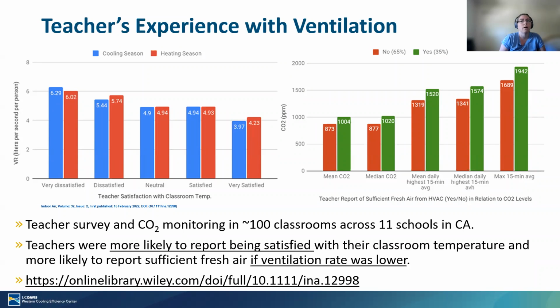Our hypothesis is that as you close down outdoor air dampers, the comfort of the classroom stabilizes. So there's a motivation for facilities to close down outdoor air dampers in response to teachers' thermal comfort complaints. For example, in the summer, we've got our outside air damper set how it's supposed to be, and we're running the air conditioning system, and the compressor is kicking on and going off, kicking on and going off. Every time it cycles off, hot outdoor air is coming in through the ventilation system and heating up. You get these hot drafts blowing on you, which causes discomfort.